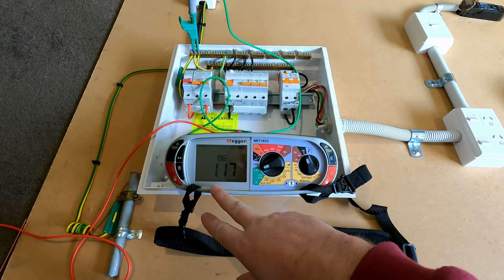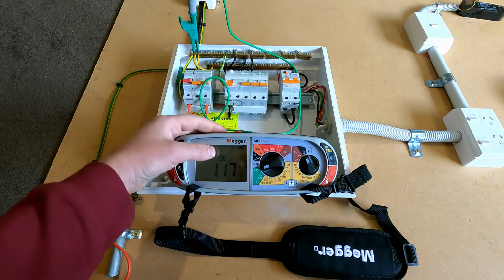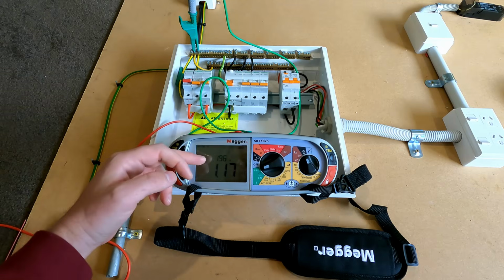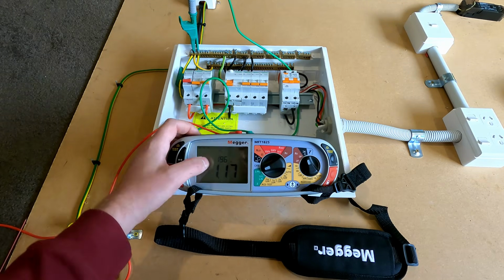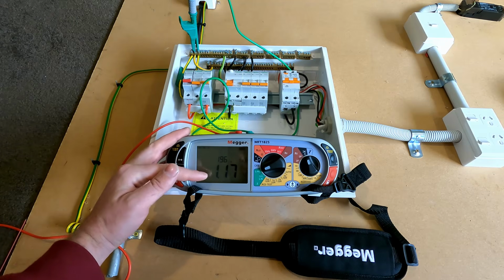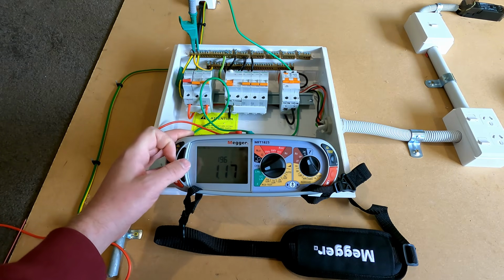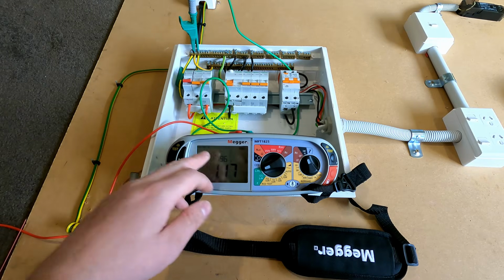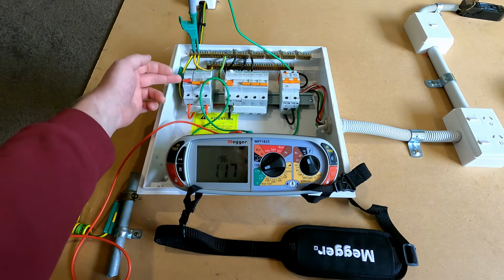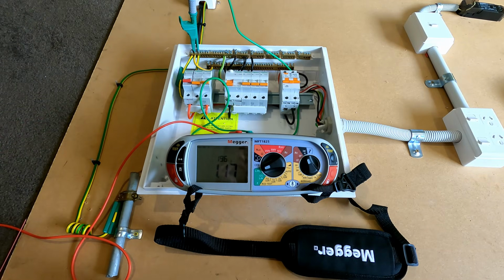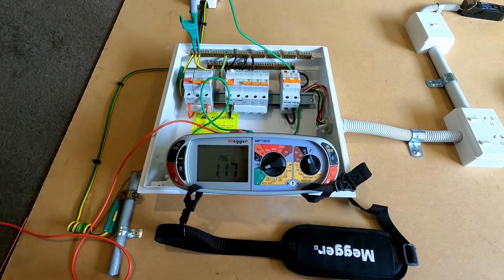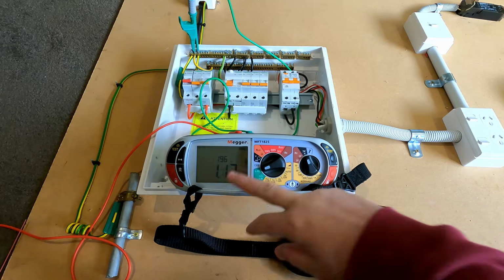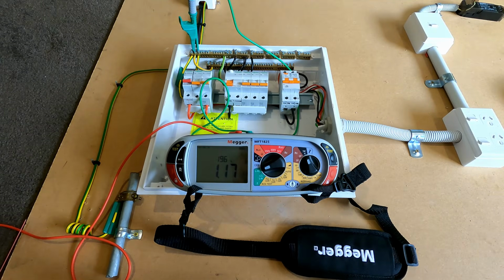So this reading here that we've come up with is our impedance, and then the one above it is our prospective short circuit current. That is just voltage over impedance, so 230 divided by 1.17 equals 196 amps. So this fault current produced is going to be high enough to trip the circuit protection. It's lower than that 6 kiloamp rating on the switchgear. Now with our impedance result, you want to go through and verify under table 8.1 whether or not your circuit protection is adequate to disconnect within 0.4 seconds.